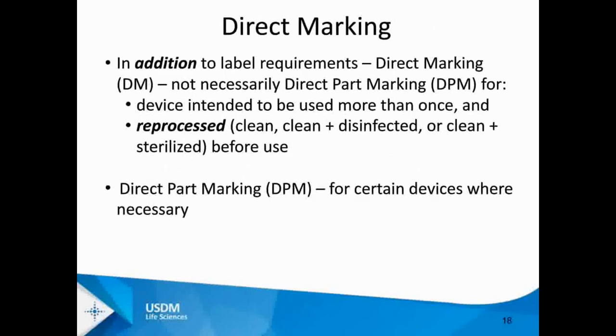There are also direct marking requirements. Devices intended to be reused and reprocessed between patient use — cleaned, disinfected, or sterilized — need the UDI on the device itself, in addition to label requirements. This is called direct marking, which covers a wide array of reusable products. Note: direct part marking is a subset of technologies; the FDA requirement is 'direct marking,' not specifically 'direct part marking.' You may fulfill it via direct part marking, but that is not mandated.